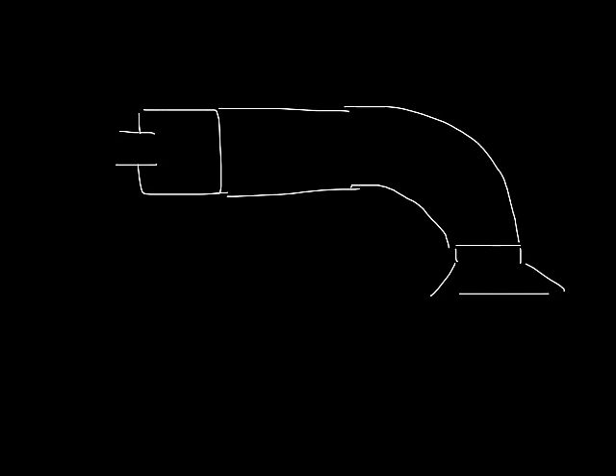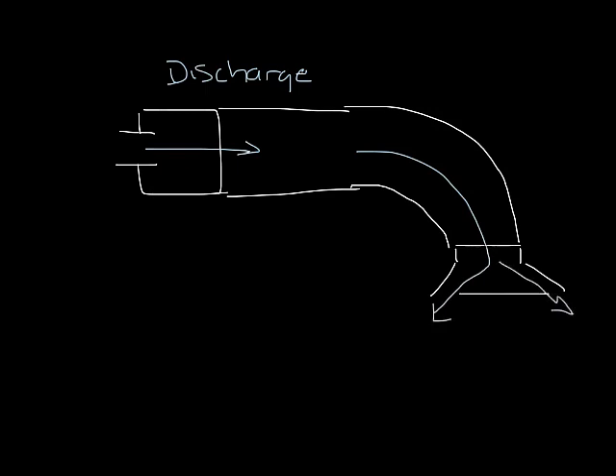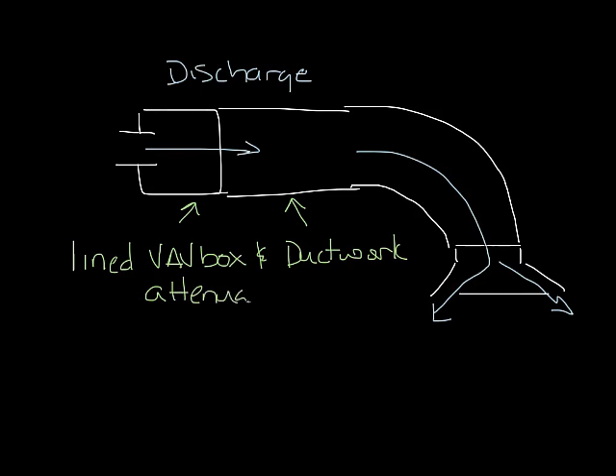So now let's look at discharge sound. Let's draw our single duct box again, and duct it out to a diffuser. Discharge air flows through the box, down the duct work, and then out the diffuser into the space. Duct work is usually lined, and lined duct work is an excellent attenuator of discharge sound from the box. The diffuser is usually a flex duct, which is also an excellent attenuator of VAV box sound coming down the duct work. It can reduce the mid frequencies by 20 dB or more.